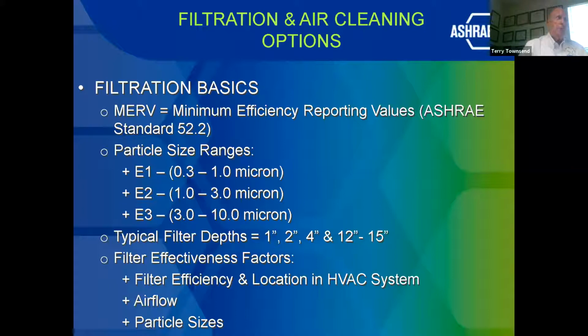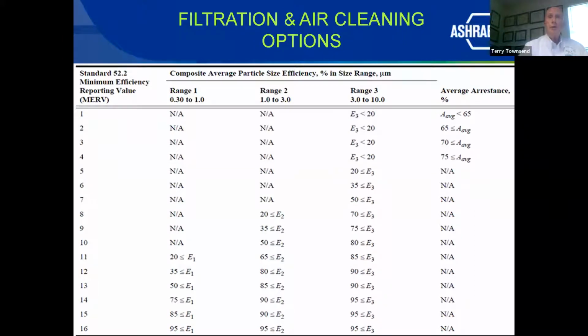So now for your filtration basics, which are in Standard 52.2, we talk about the minimum efficiency reporting values. Hopefully you are familiar with this. They're based upon 3 different particle sizes, and your typical filter depths are anywhere from 1 inch to 12 to 15 inches for HEPA filters. Filter effectiveness factors are efficiency, location, airflow, and particle sizes. This gives you, from Standard 52.2, the MERV ratings 1 through 16 and the range they are effective for range 1, 2, and 3 particles.